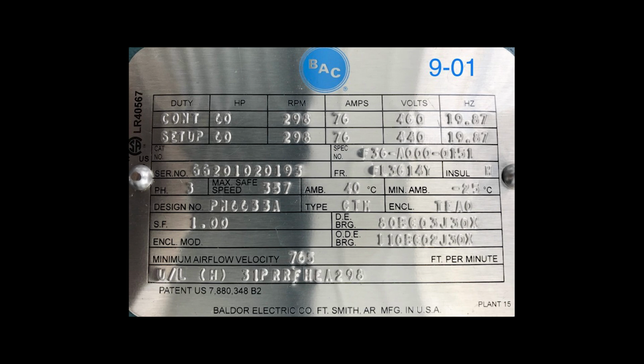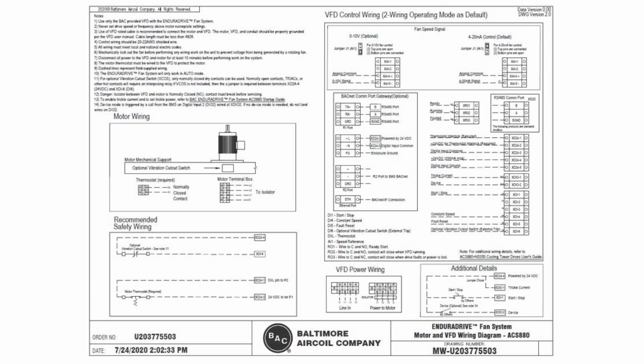Next, locate the nameplate on the Enduradrive motor. Once again, write down the information you'll need during the setup and take a picture of the nameplate for later reference. You will need to write down the horsepower, the RPM, the amps, the volts, and the hertz. Once you've gathered the necessary information from the motor's warning label and nameplate, it's time to ensure the wiring connections on your motor match the wiring diagram. You should have a copy of the wiring diagram for your unit in the packet that came with the unit.